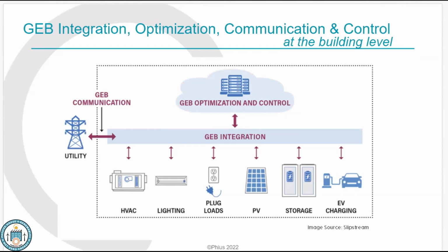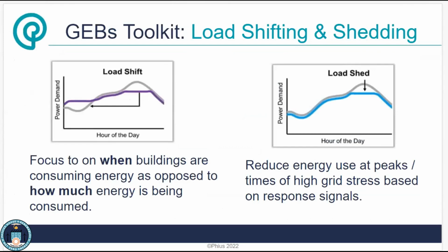On the next slide, there are two ways buildings can respond: load shifting and load shedding. With a load shift, you take a load you might have—for example, domestic hot water heating—and make it during the day when we've got solar, storing it in a tank. We've just shifted it to a different time of day to reduce a peak. A load shed is the super insulated passive envelope—it pulls down those peaks because we don't need as much energy to heat the building, since the envelope is doing more work. So shift is taking the same load and moving it; shed is eliminating it completely.